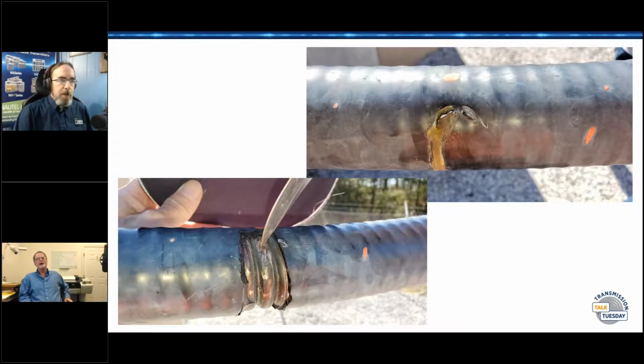I would say this probably happened when someone was doing work on the tower and dropped something. There's another case coming up that's a much more expensive, worse example. You look at that and think, okay, is it just the jacket messed up, or do we have a problem? As you can see in the bottom left, when we cut some of the jacket off, there was a pinhole through there. This one's on a nitrous tank. Nitrous isn't incredibly expensive, but it doesn't work if you've got a leak and the tank goes dry.